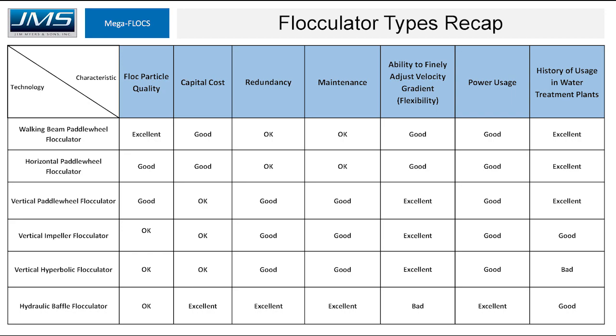As far as maintenance, the baffle wall flocculator is very user-friendly with low maintenance. The vertical units are easily accessible for maintenance. Horizontal and walking beam require just a little more maintenance activity. For finely adjusting velocity gradient, the vertical units offer the most flexibility because you can adjust the speed of one reel independently. With horizontal and walking beam, you can adjust drive speed but it affects many reels at once. For baffle wall flocculators, almost no adjustment is possible.